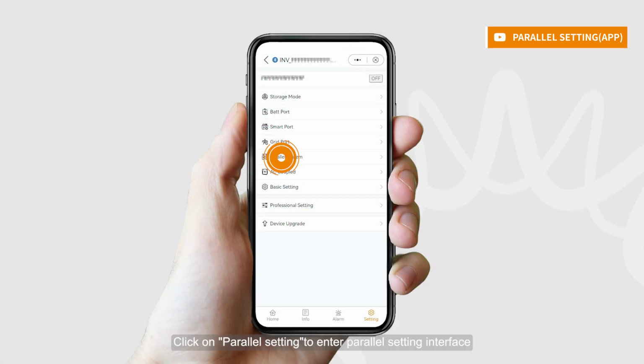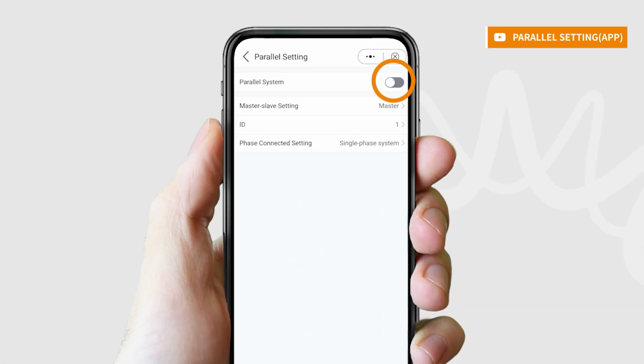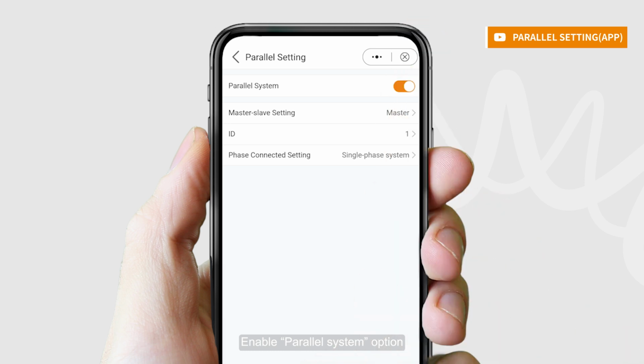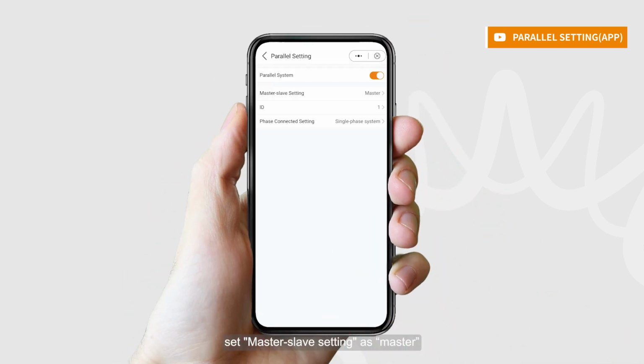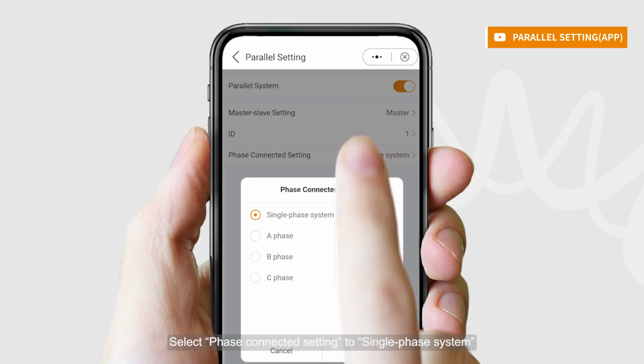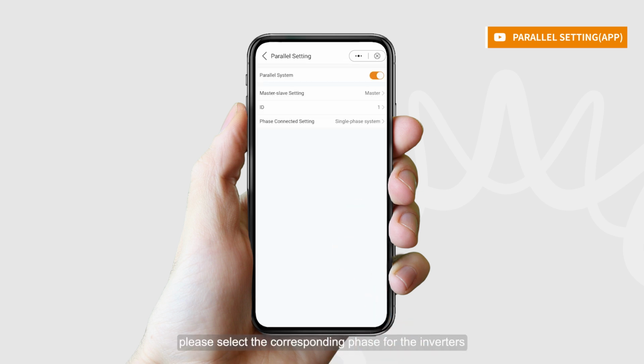Click on Parallel Setting to enter Parallel Setting interface. Enable Parallel System option. Select one inverter as the master, set Master Slave Setting as Master, and set the address to 1. Select Phase Connected Setting to Single Phase System. If forming a 3-phase system, please select the corresponding phase for the inverters.